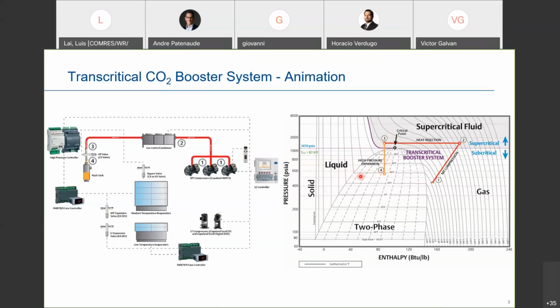When you're inside the pressure enthalpy dome here, you've got on the right 100% vapor, on the left 100% liquid. So when you fall in the middle, you know right away you've got a percentage of gas and a percentage of liquid. And that's what happens in the flash tank. You've got liquid in the bottom, and flash gas on top of that liquid, like any liquid-vapor interface would have. That liquid now gets fed to all of your medium temp electronic valves. If you've got 20 cases or you've got 75 cases, it doesn't matter. And then it feeds all your low temp cases.